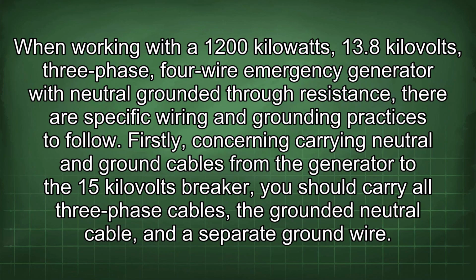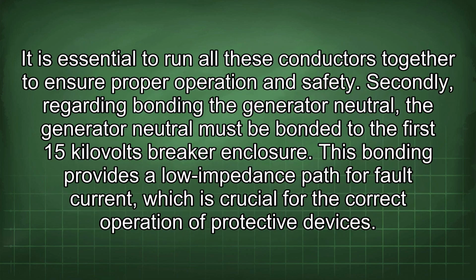When working with a 1200 kilowatts, 13.8 kilovolts, 3-phase, 4-wire emergency generator with neutral grounded through resistance, there are specific wiring and grounding practices to follow. Firstly, concerning carrying neutral and ground cables from the generator to the 15 kilovolts breaker, you should carry all 3-phase cables, the grounded neutral cable, and a separate ground wire. It is essential to run all these conductors together to ensure proper operation and safety.